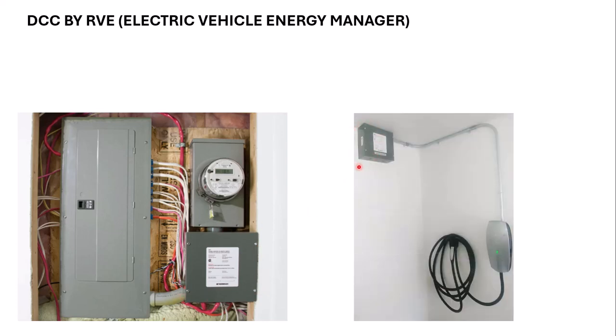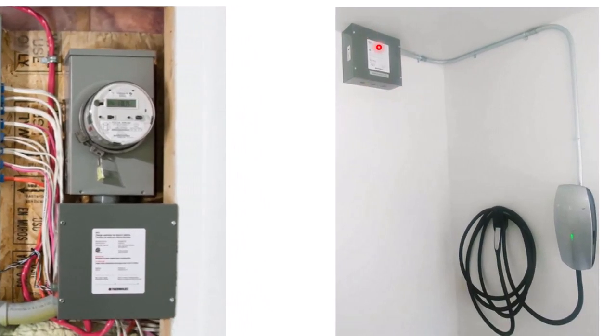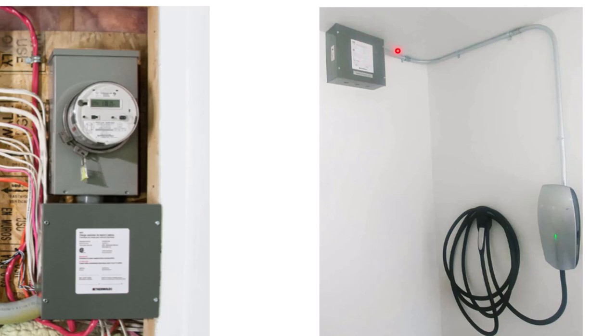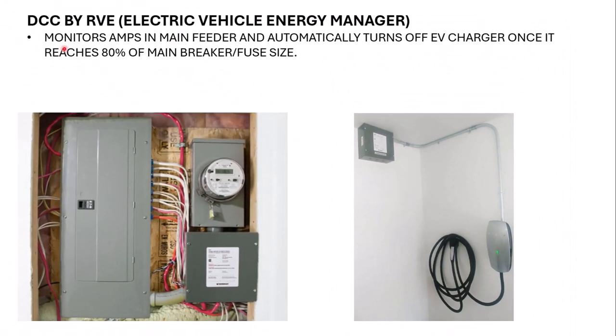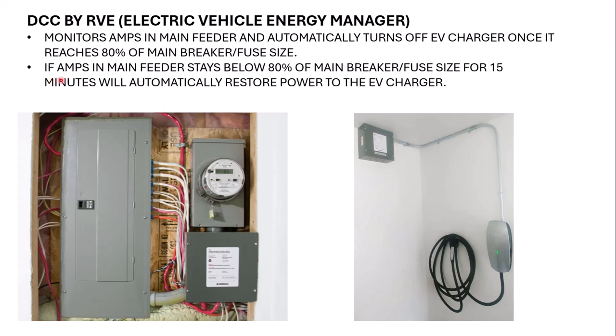And this is a picture of another installation of it. So the box is right here. This is where the switching occurs. And then you can see the conduit will connect the electric wiring to this charger. And the way it works is it monitors the amps in the main feeder and automatically turns off the EV charger once it reaches 80% of the main breaker fuse size. And then if the amps in the main feeder stay below 80% of the main breaker fuse size for 15 minutes, I think there are different settings within the equipment, but 15 is one of them, then it'll automatically restore power back to the EV charger.